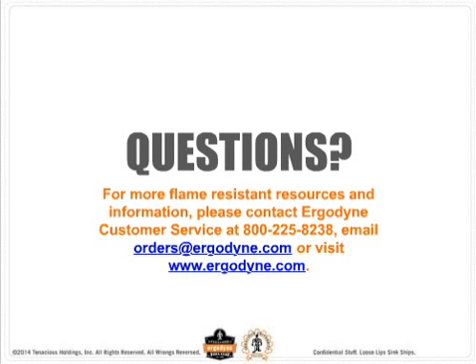Is there a complete table available for selecting HRC levels based on voltage or conditions? This individual is interested in putting labels on their panels and breakers. Yeah, sure. I would suggest that person look at NFPA 70E. I believe it's Table 130, and that is going to give you a list of exactly what I showed you on the screen here, which was just a very small snippet. It's going to break down each task that a worker would perform so that you know exactly what's required depending on the task.